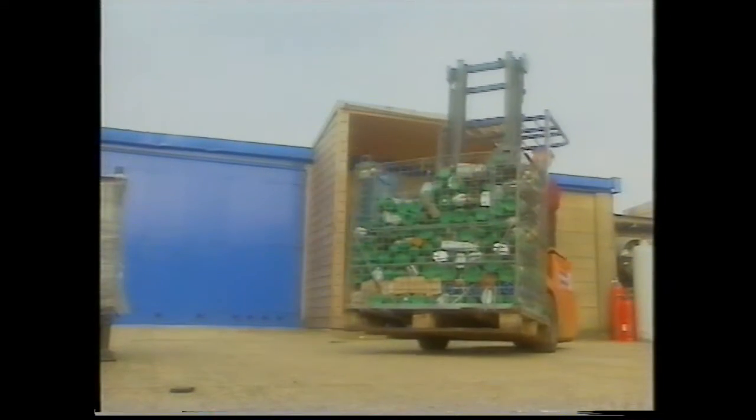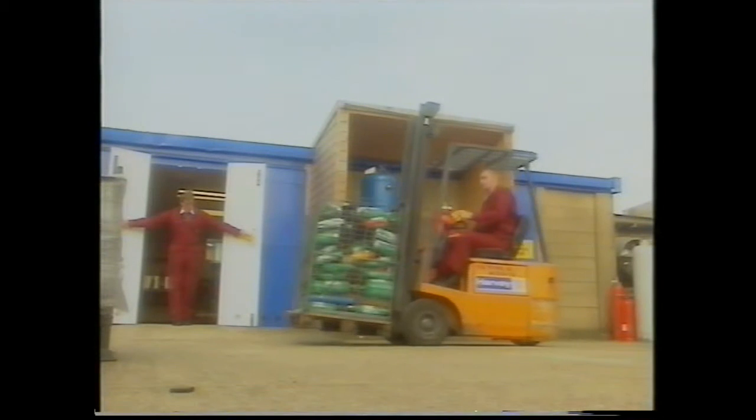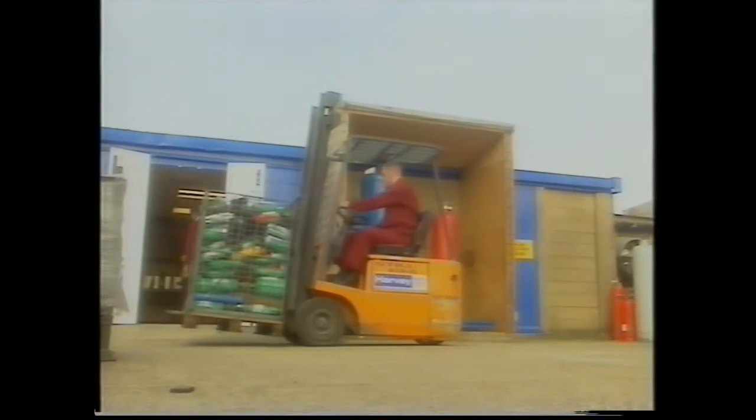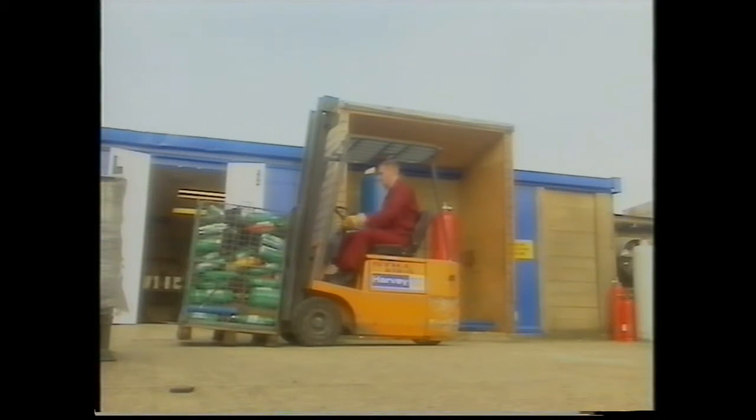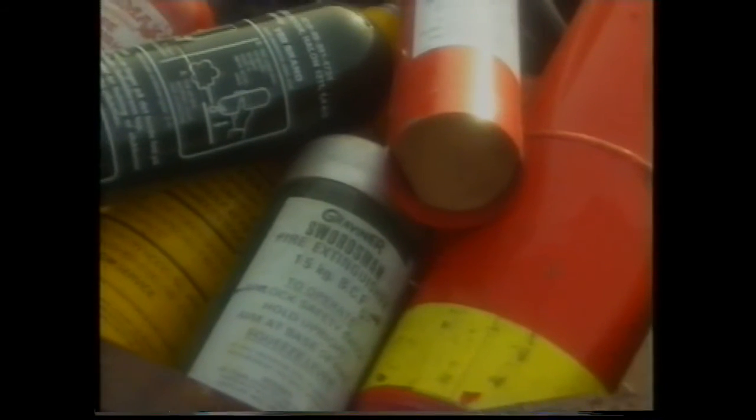At a typical installation operated by Chubb's sister company, Pyrene, a large quantity of portable extinguishers containing Halon 1211 have already arrived for processing. On the recovery unit, they are first connected to one of three inlet manifolds. A typical day may see a throughput of several hundred portable extinguishers with up to 21 individual units processed at a time, regardless of model or individual capacity.